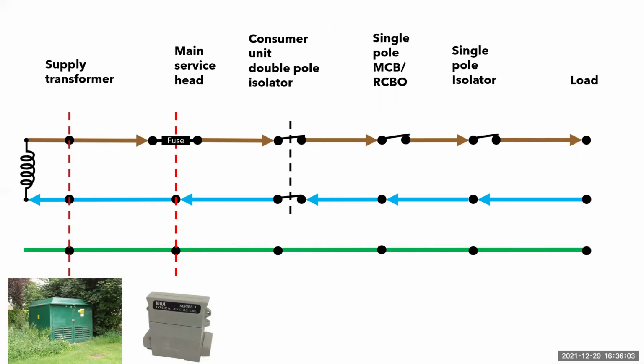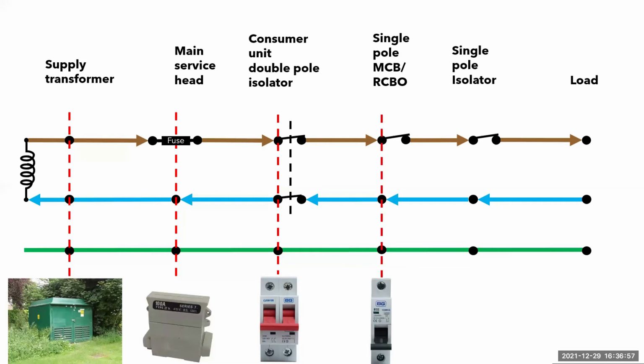I've left the electricity meter out for clarity, but this would usually go between the main service head and the consumer unit. If you look at the first few pages of the on-site guide, you will see the traditional arrangement. After this, we have a double pole main switch. You need to check whether this can be switched off under load. I will talk about that at the end of this slide. And this then leads to the single pole MCB or RCBO that is protecting the circuit.